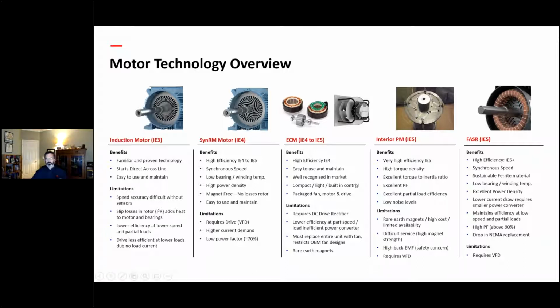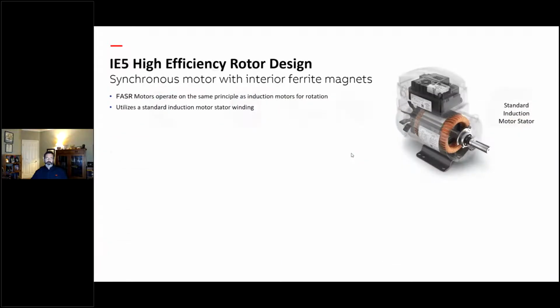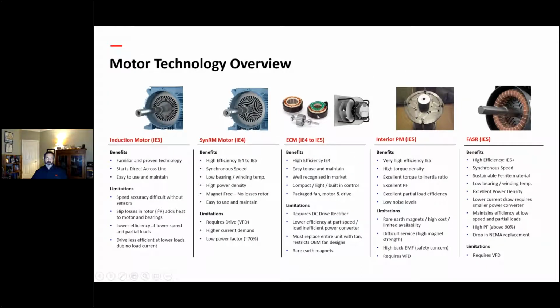The next one, this one's been out for a number of years. It's an electrically commutated motor, and they're sold typically as just a package. So they're not usually sold just as the motor. They have to have a drive on it. It's a DC permanent magnet controller, and they're usually sold as these packages.